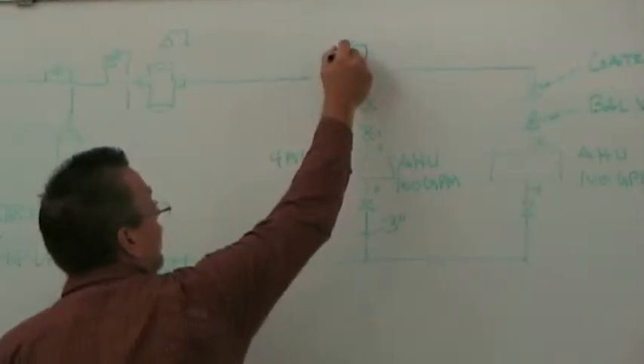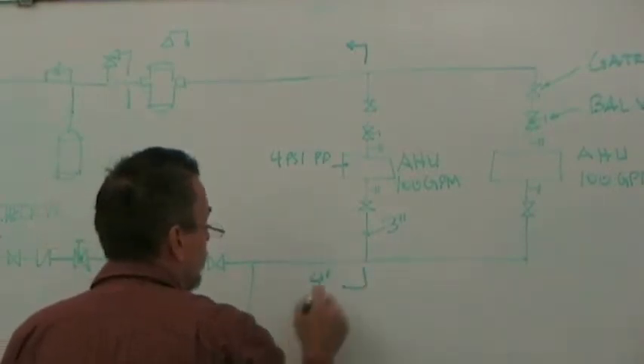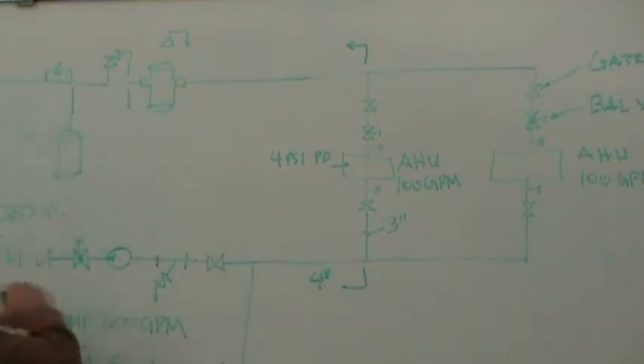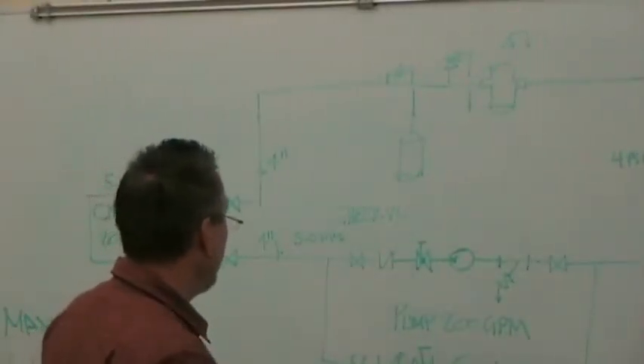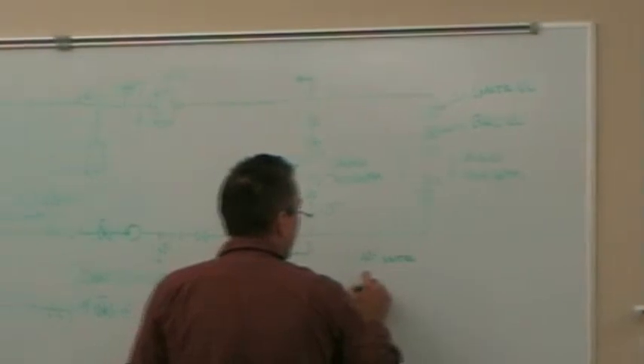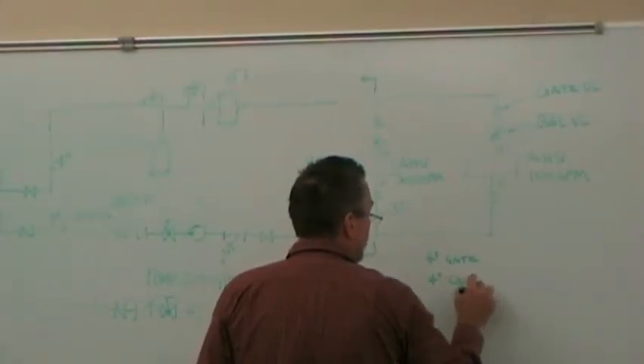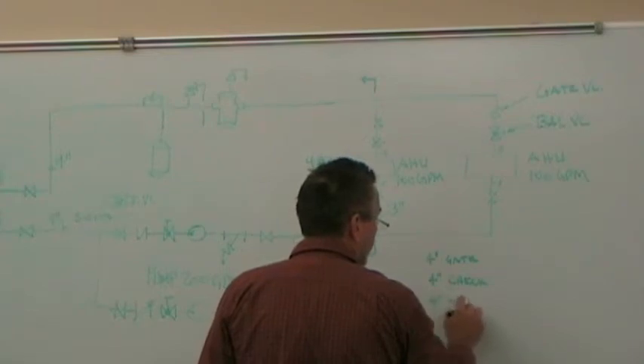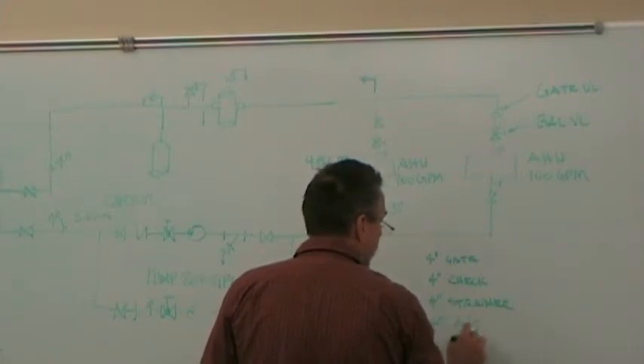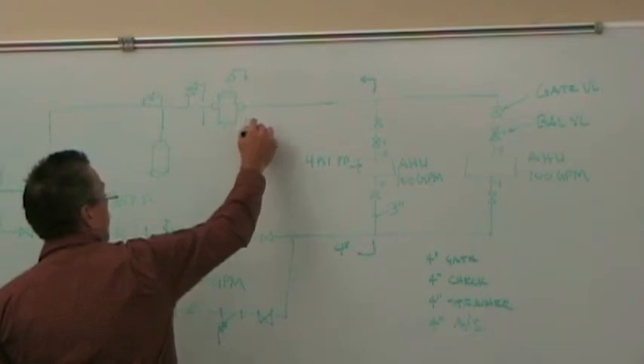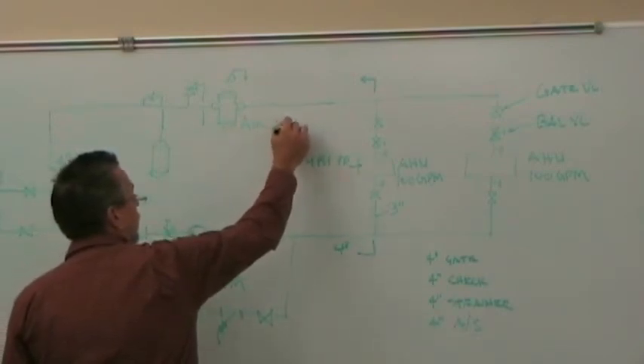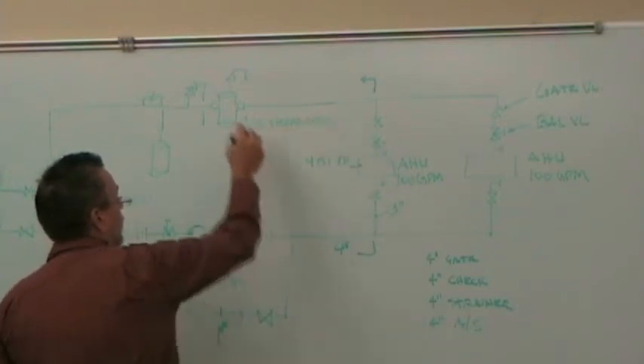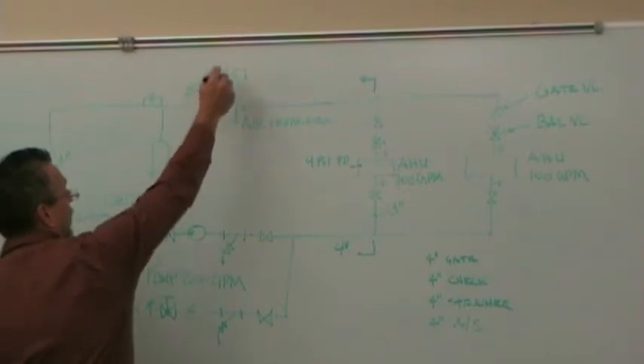And from here to here, it's 4-inch. And it's 200 gallons a minute. So I start looking at my components, okay? So I've got a 4-inch gate valve, 4-inch check valve, 4-inch strainer, 4-inch air separator up here, the purpose of that is to remove the air in the line, go through an automatic air vent.